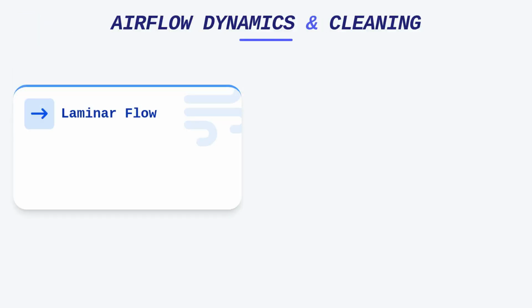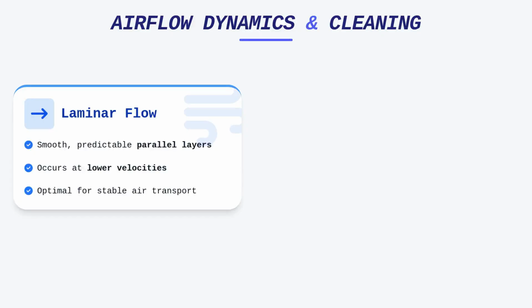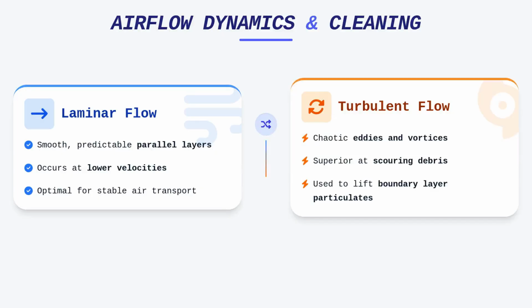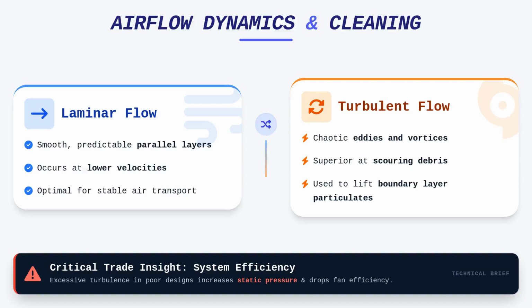When we observe how air travels, we must distinguish between laminar and turbulent flow, as both serve different functions in our trade. Laminar flow is smooth and predictable, typically occurring at lower velocities where air moves in parallel layers. In contrast, turbulent flow is characterized by chaotic eddies and vortices, which are significantly more effective at scouring debris from contaminated surfaces. Within the ductwork, we often intentionally induce turbulence during the cleaning process to lift particulates that have settled on the boundary layers. However, excessive turbulence in a poorly designed system leads to drop-offs in efficiency and increased static pressure, working against the fan's output.